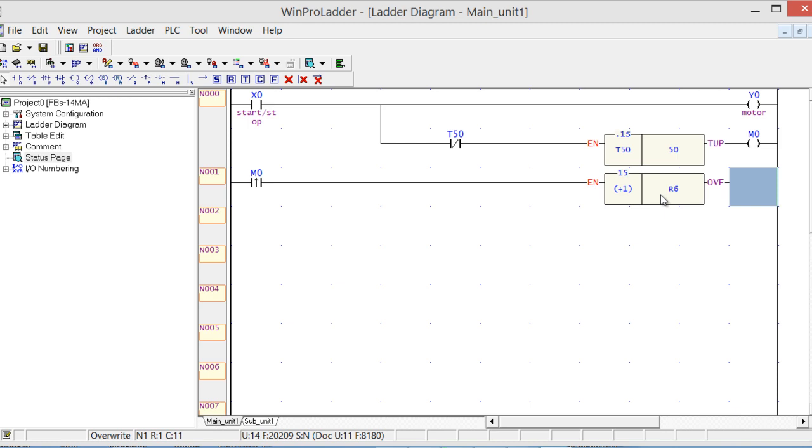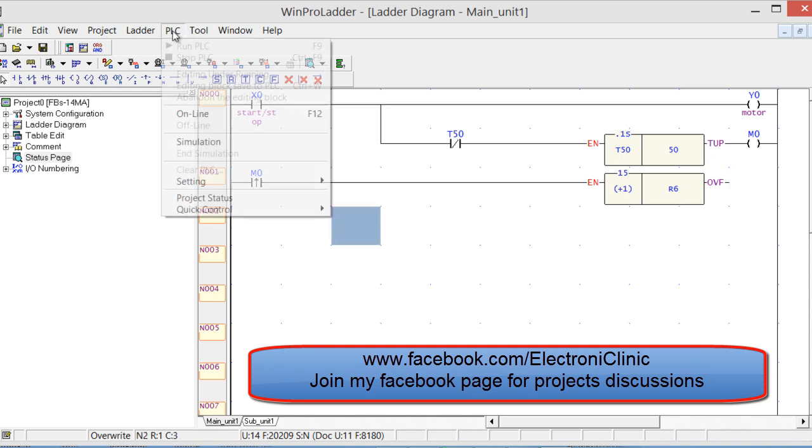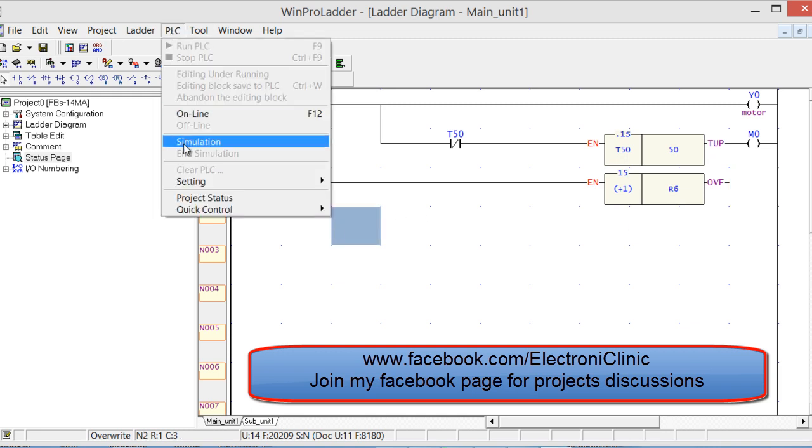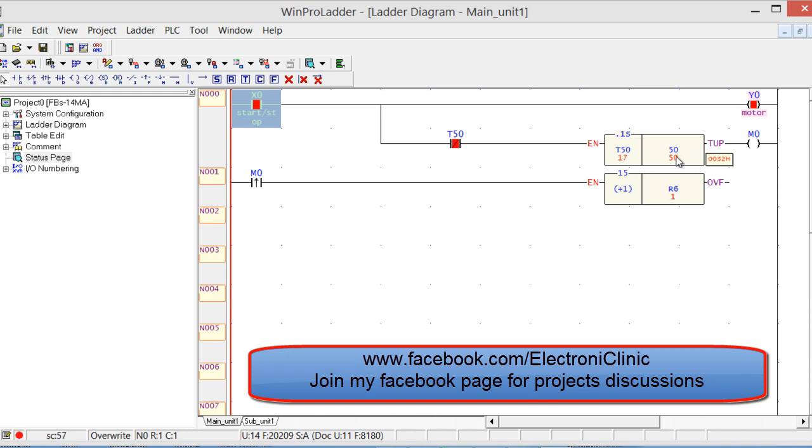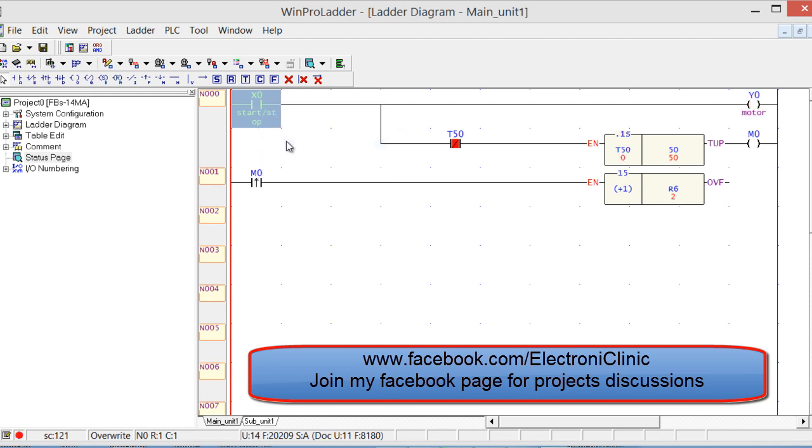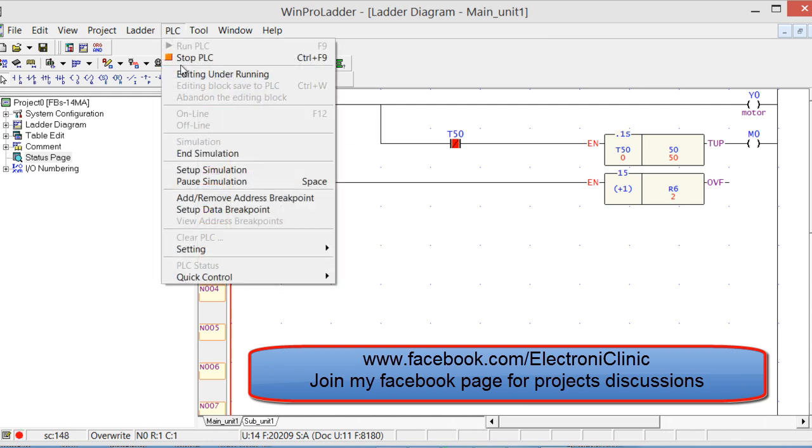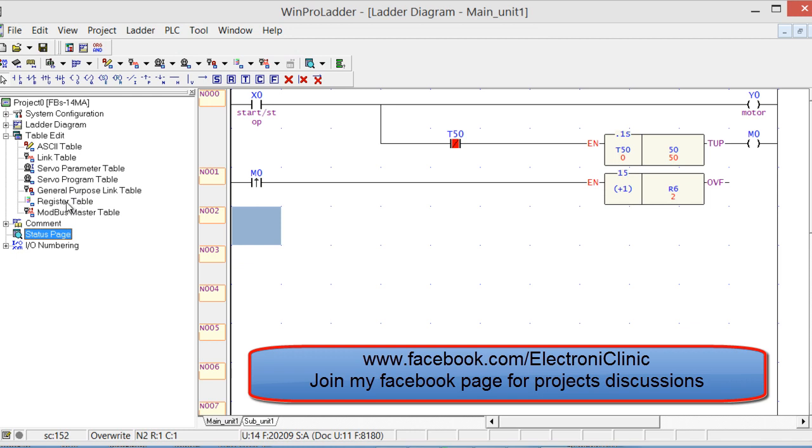If we put 600 over here, it means 60 seconds, so it will start counting minutes. But for now we just keep it 5 seconds. Let's check whether it works or not. Click on Simulation, Run PLC. While the switch is closed you can see that the timer is running. After 5 seconds it has incremented 1, now it will become 2, 3, 4. And we'll stop that. It's working.